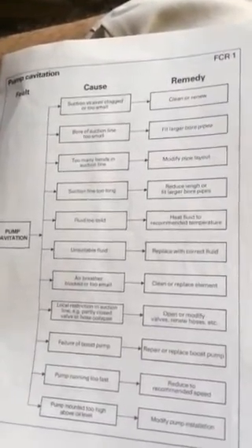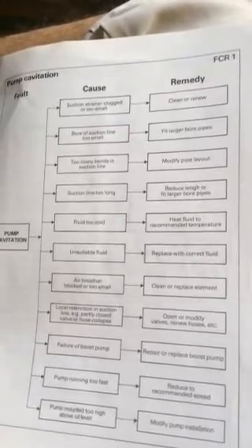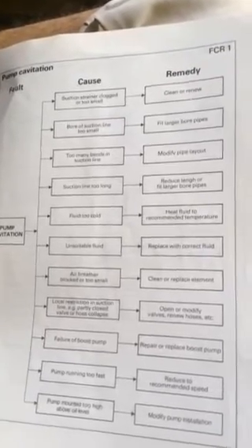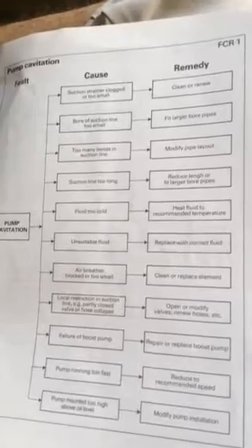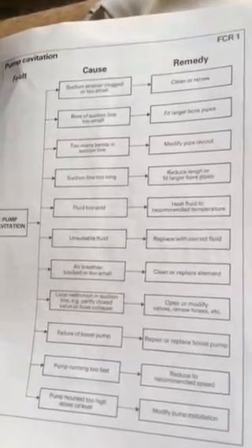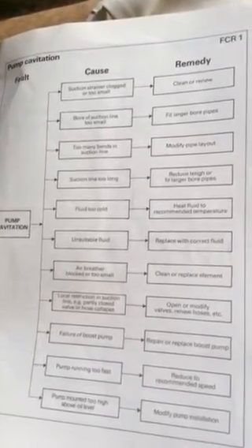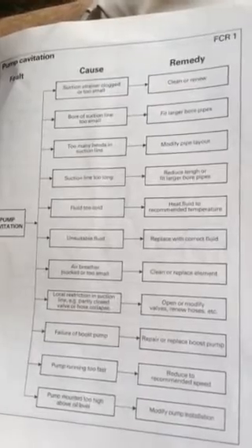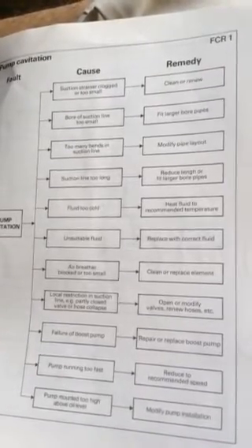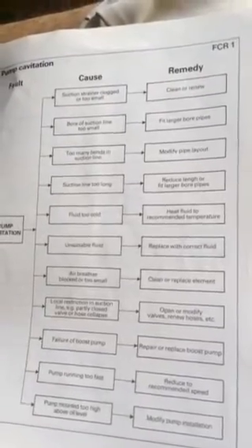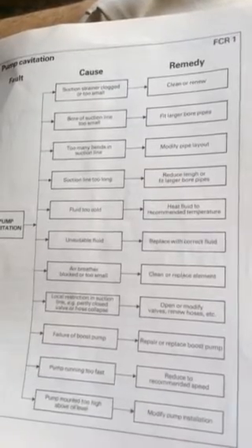We are into logical troubleshooting in hydraulic systems, and this is the pump cavitation problem. What is the cause of the cavitation problem? Suction strainer clogged or too small. What's the remedy? Clean or renew.